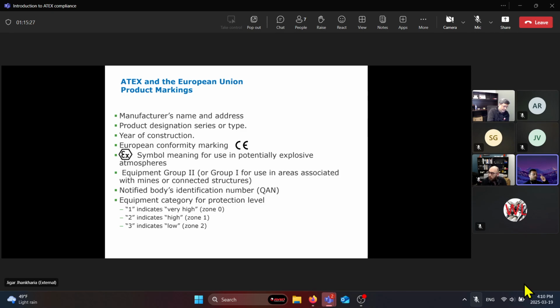And like I mentioned, this is pretty much what the marking symbol would be. Next to the CE would be our notified body number, followed by EX, and then the equipment group, which is going to be group 2 for you guys. The notified body identification number, usually we just include it after the CE mark, and then the equipment category.